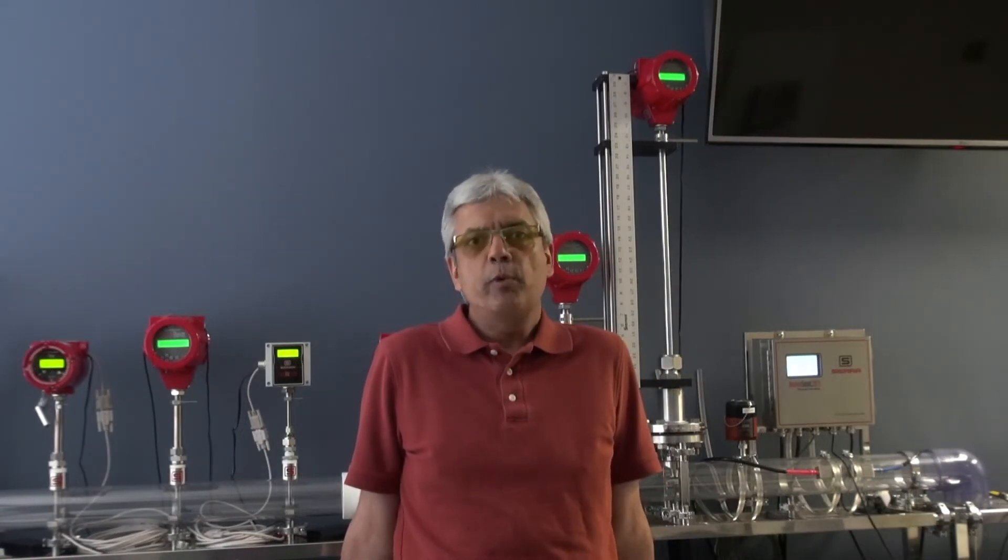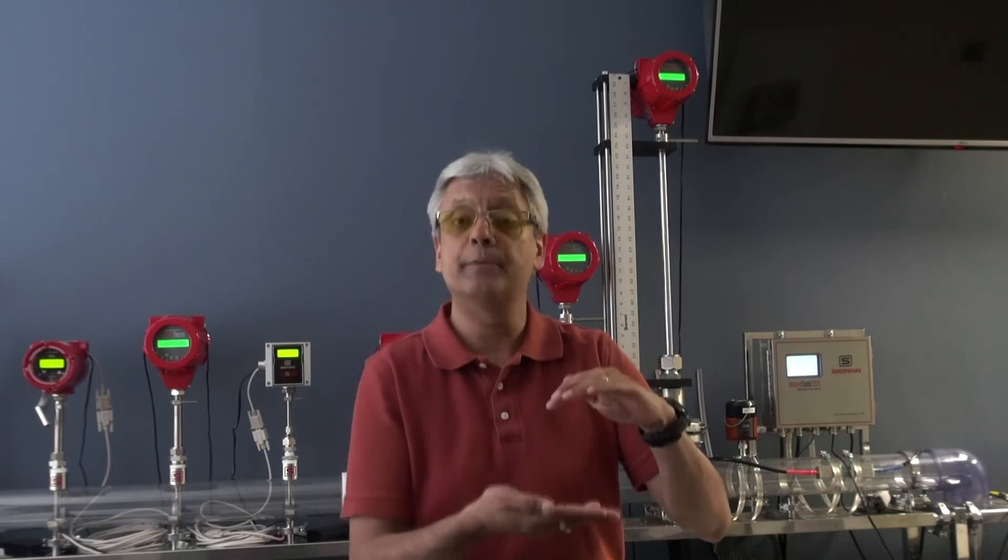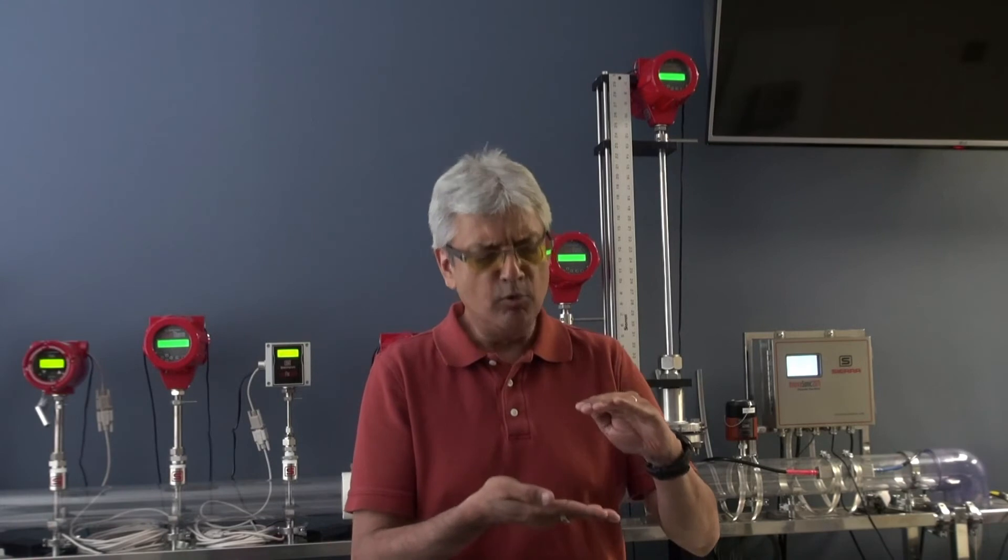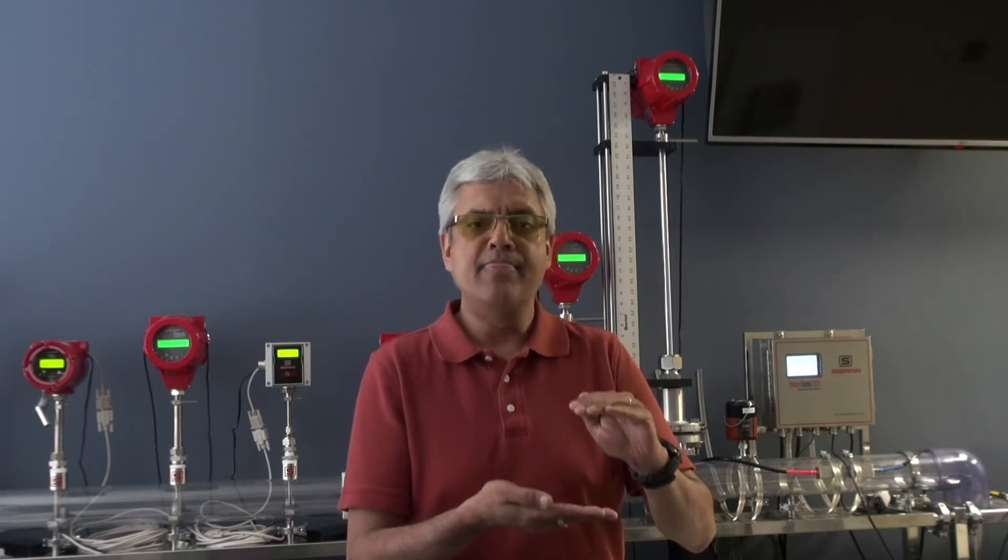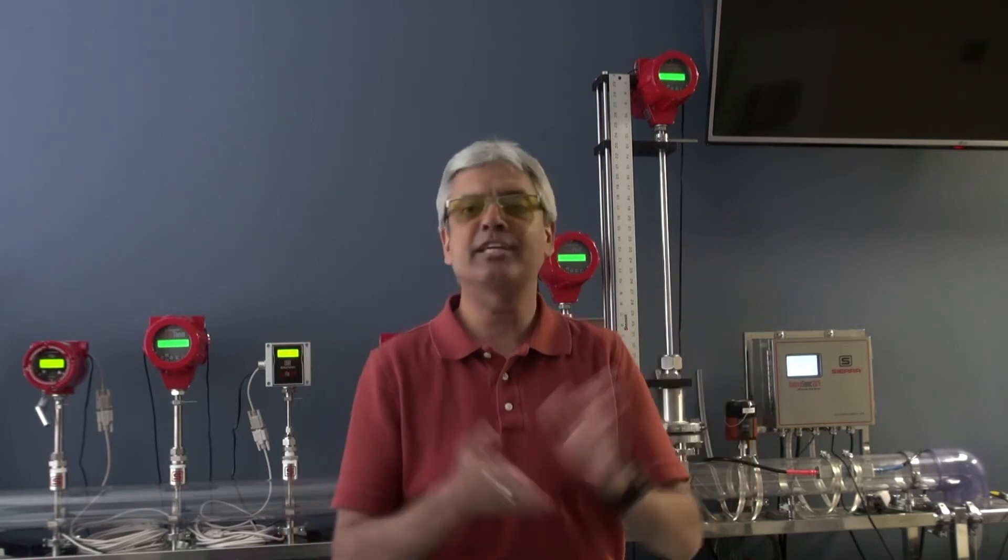Some of the problems that we have seen in the field, a very common one is the pipe size is wrong. They'll tell us initially that they want a 4-inch pipe size, the inner diameter, and so we'll calibrate the system for a 4-inch pipe. And they'll go and install it, and guess what? It's not really a 4-inch pipe. It's a 6-inch pipe.